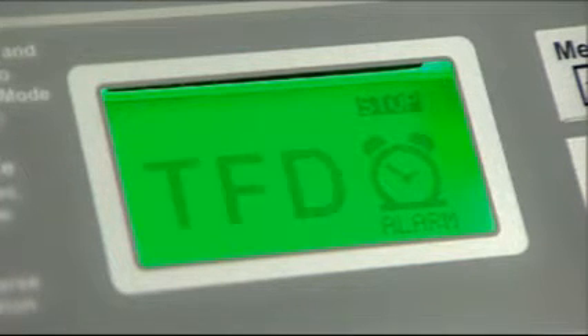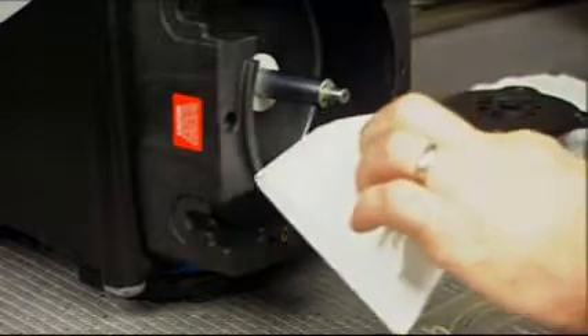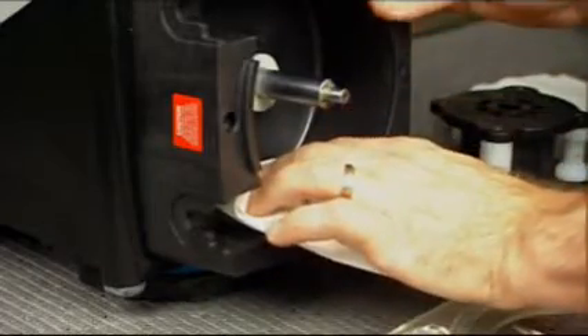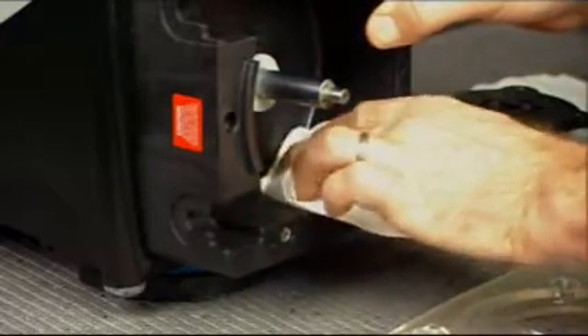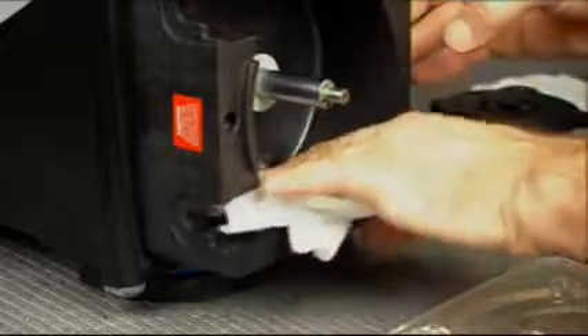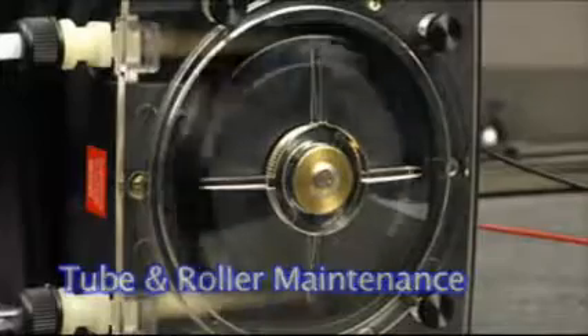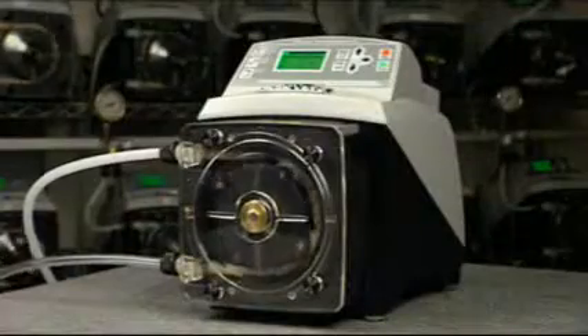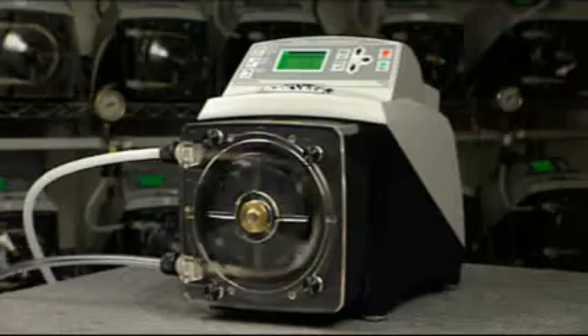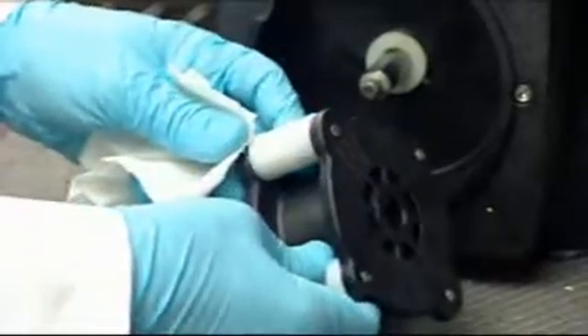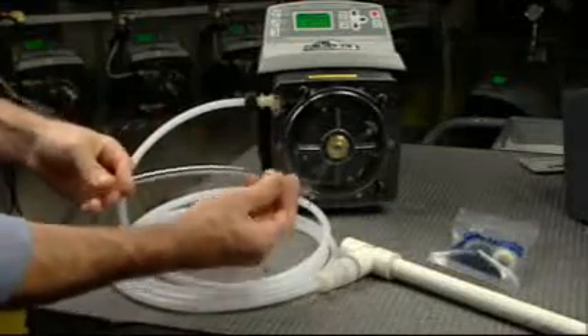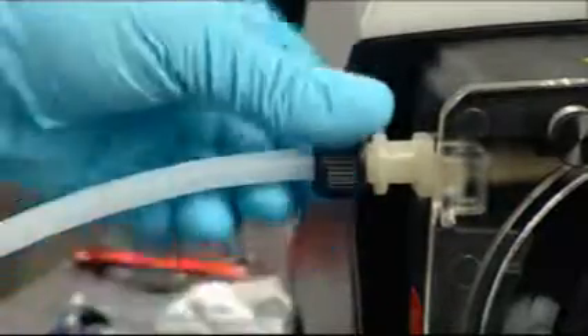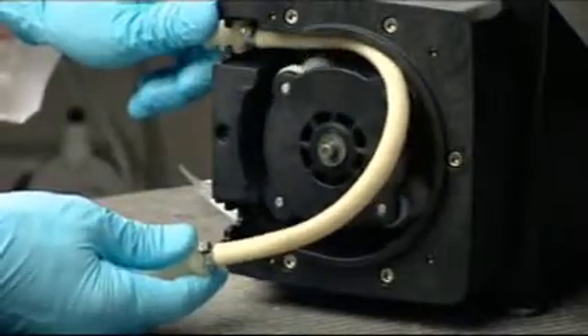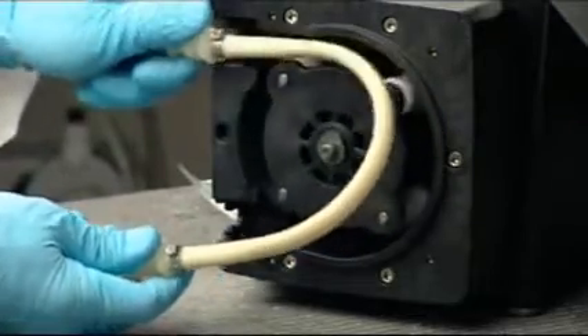An alarm icon will be displayed indicating that the pump tube should be replaced. Be sure to wipe clean any chemical or debris from the inside of the pump head and from the TFD system sensor pins. The pump tube should be replaced periodically when worn or in the event of a rupture. The roller assembly, pump head, suction tubing, and discharge tubing should be inspected at this time and cleaned or replaced if necessary. The A3's power-assisted pump tube replacement system makes changing the pump tube quick and easy.